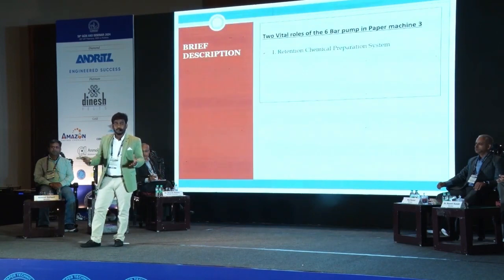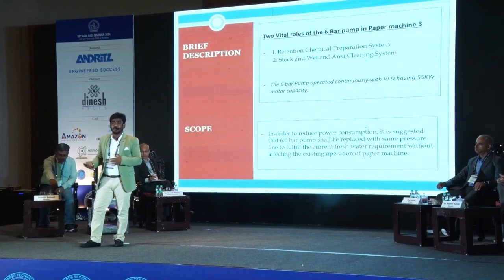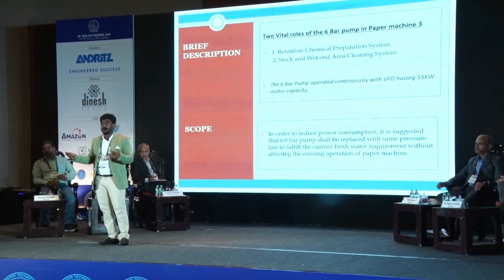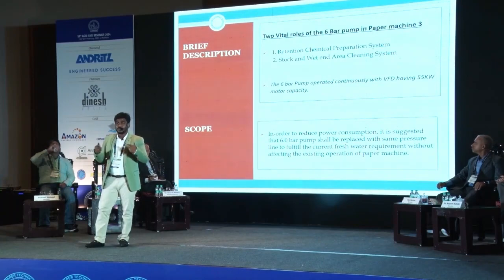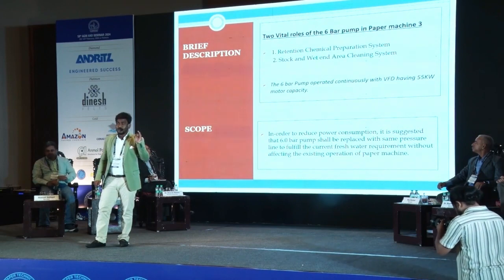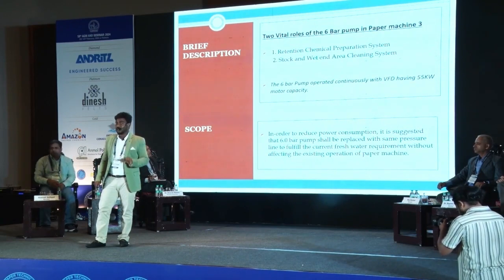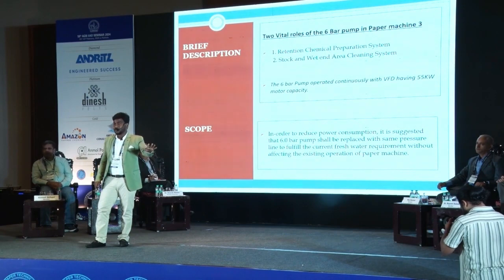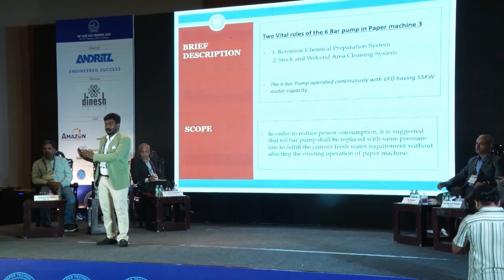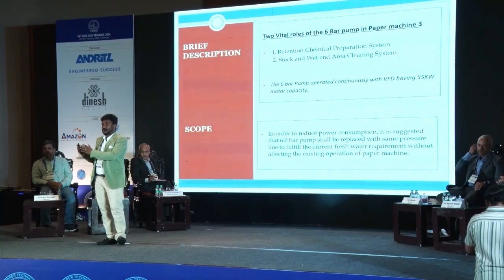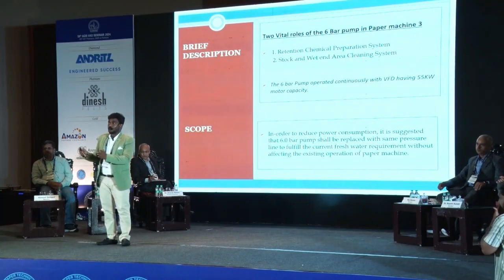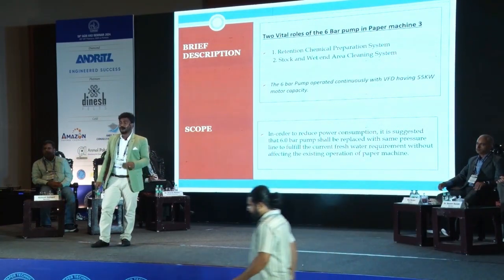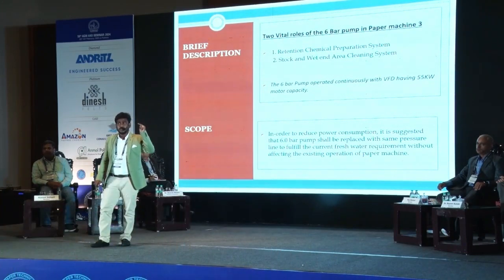In the paper machine, we have different pressure pumps for the process requirement, like 3-bar, 6-bar, 30-bar and 70-bar for the high pressure showers in the wet end. The main purpose of the 6-bar is to supply the desired water pressure for the retention chemical preparation system and for cleaning of stock and the wet end area during necessary times. Other than the retention chemical preparation system, the need of cleaning will be required only when there is a machine stoppage or break. So there is scope for energy saving if we could find an alternative source to service the need of the retention chemical preparation system.